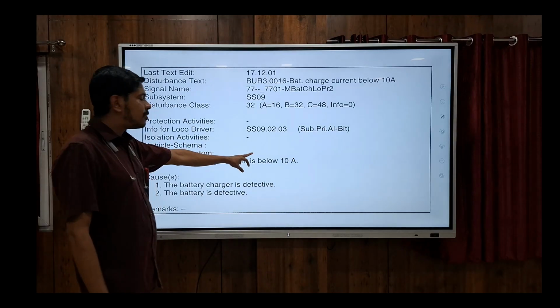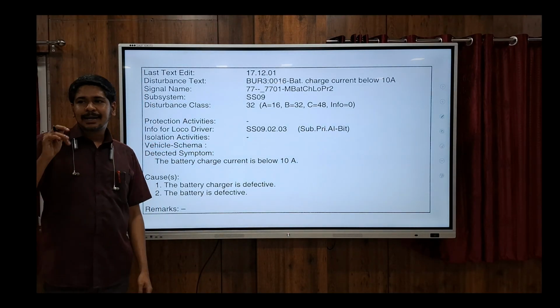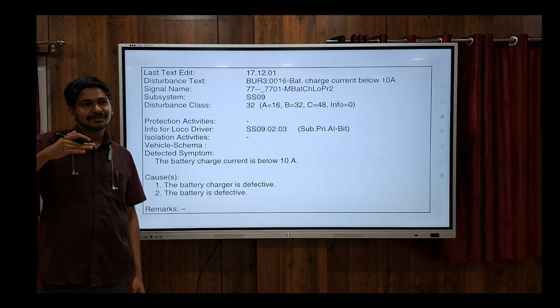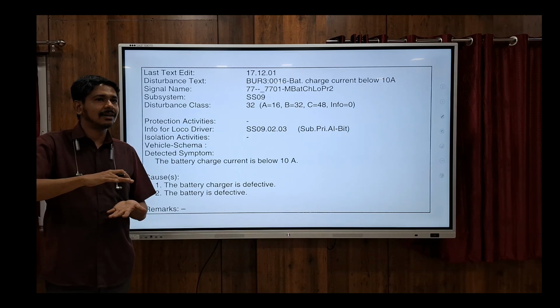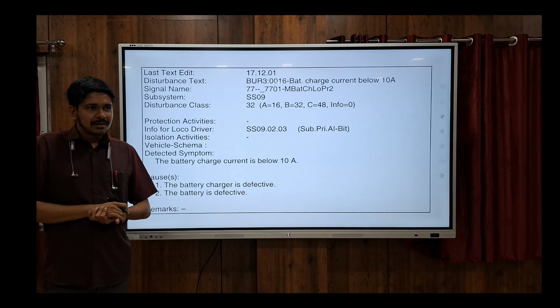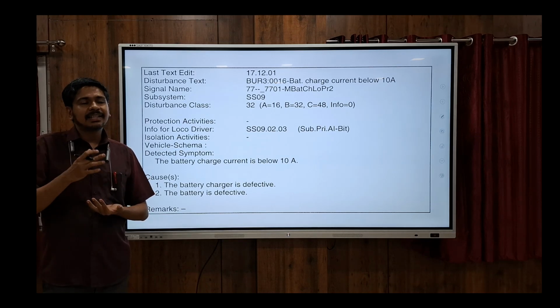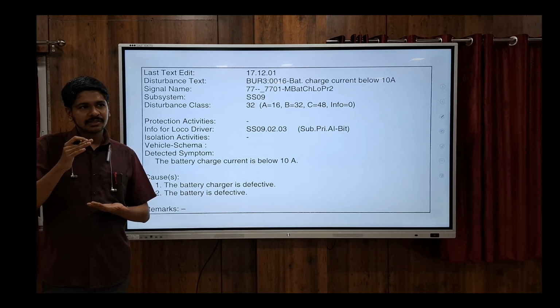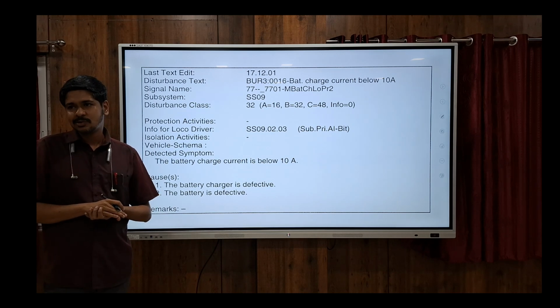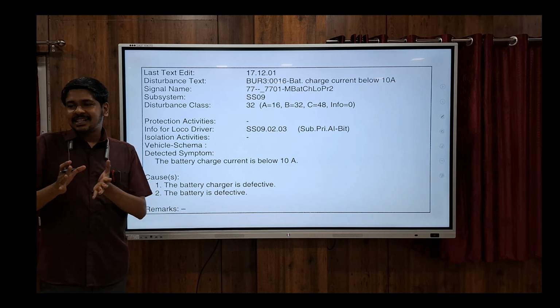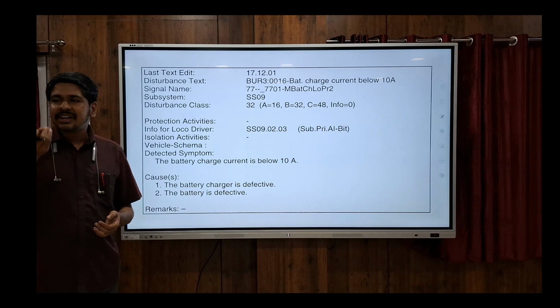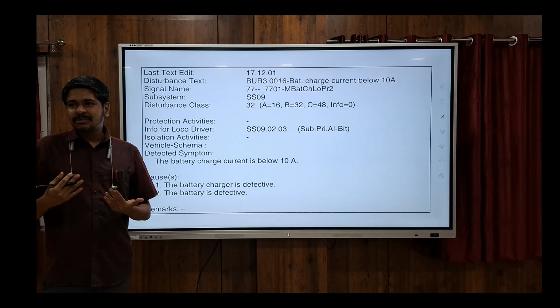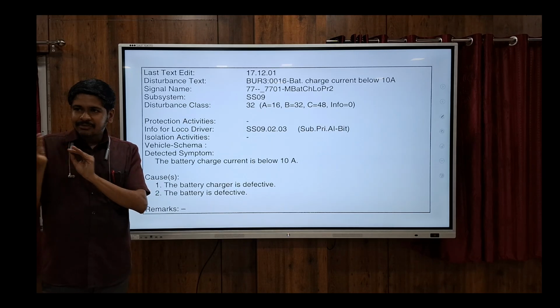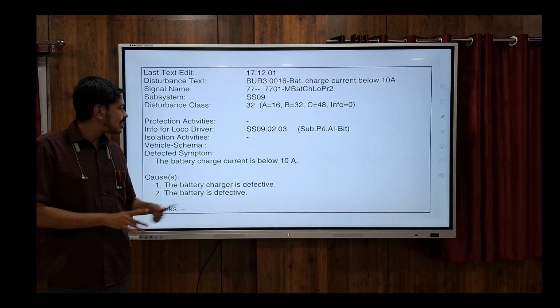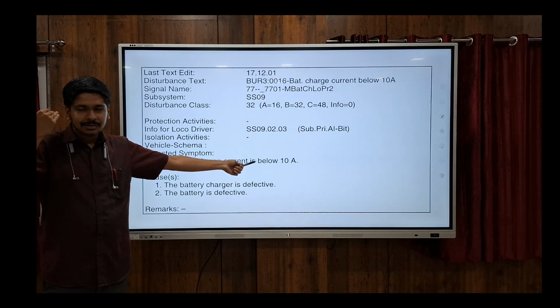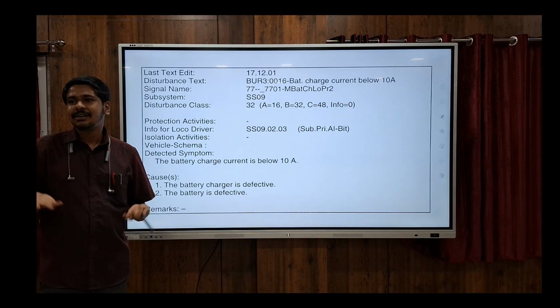Then battery charger current below 10 amps. That also comes when the battery charger is not working. Sometimes this message can come even if the battery is fully charged. Now companies like CGL have changed their setting from 10 amps to 8.1 amps. Because with fully charged batteries, if the electronics is taking very little current, the current drawn from the battery charger will be very low. At that time the current will go below 10 amps and unnecessary tripping will come.